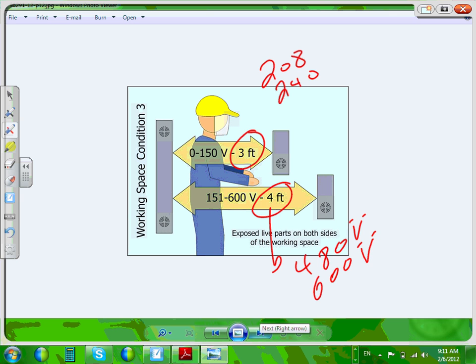For 480, 3 feet, except if you have hot equipment in front of each other and one of them is 480, it jumps 1 foot. If you have a grounded part, you jump half a foot. That's it, the summary of the whole depth. So your depth goes from 3 feet to 4 feet.